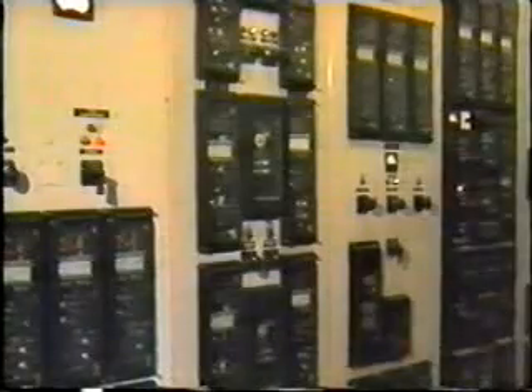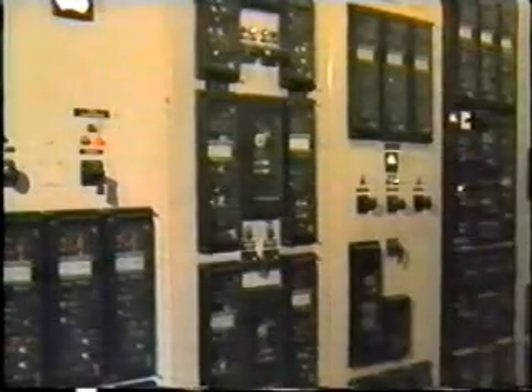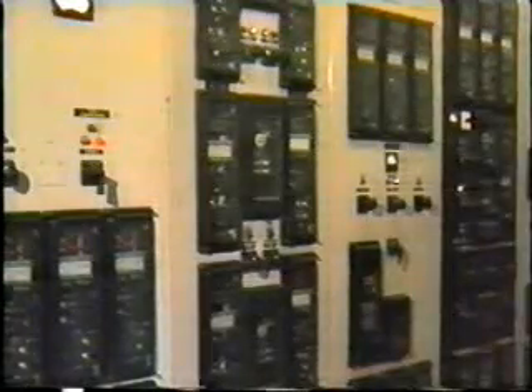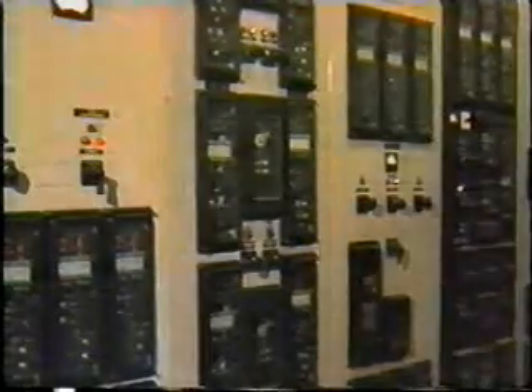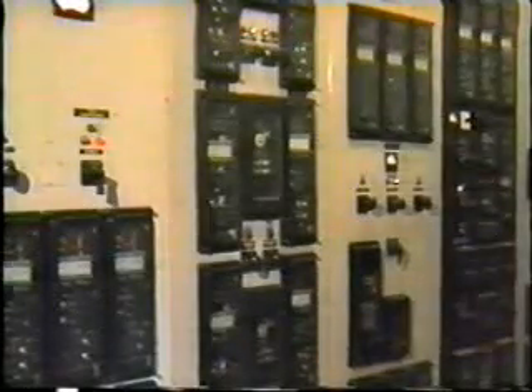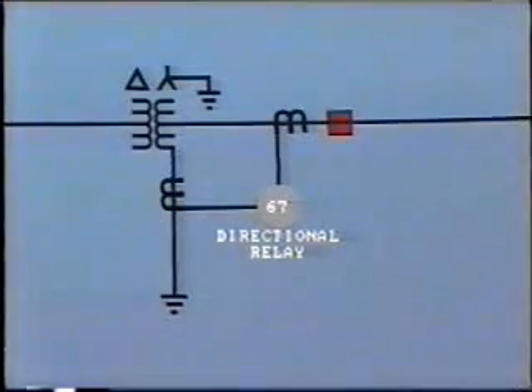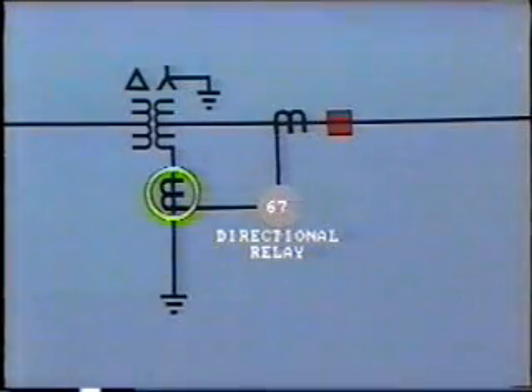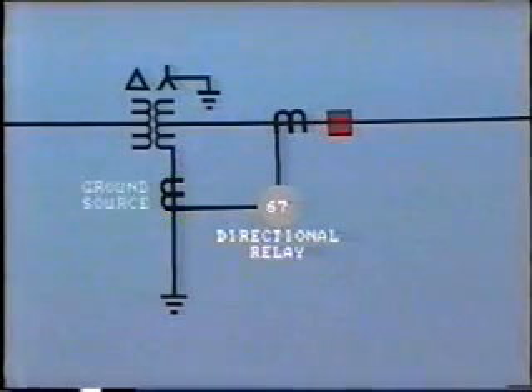We spent some time discussing directional overcurrent relays in an earlier videotape in this series. Perhaps at this point it would be worth your while to review this subject in PSP2, Segment C. As we've learned, for the directional unit to operate, a reference or polarizing quantity is required. For ground fault relays, the preferred method is by current polarization obtained by locating a CT in the supply transformer grounded neutral, like this. From a protective relaying point of view, this is known as a ground source.